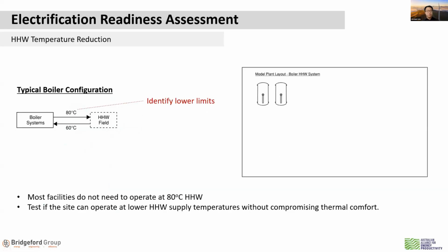So the first thing that asset owners can do at the facility is heating hot water supply temperature reduction testing. What it really entails is assessing if a typical building heating hot water system that normally delivers 80-degree water for heating can be adjusted down to a lower temperature without compromising on the building's ability to maintain the set point temperature.